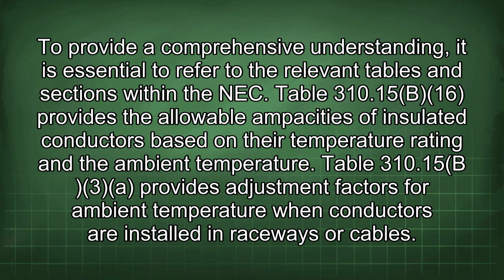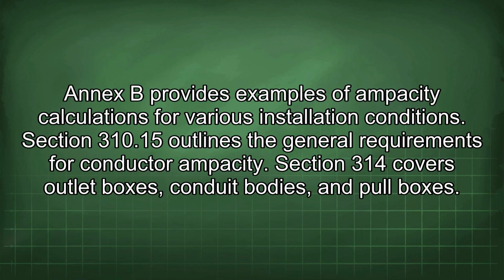To provide a comprehensive understanding, it is essential to refer to the relevant tables and sections within the NEC. Table 310.15(B)(16) provides the allowable ampacities of insulated conductors based on their temperature rating and the ambient temperature. Table 310.15(B)(3)(a) provides adjustment factors for ambient temperature when conductors are installed in raceways or cables. Annex B provides examples of ampacity calculations for various installation conditions. Section 310.15 outlines the general requirements for conductor ampacity.